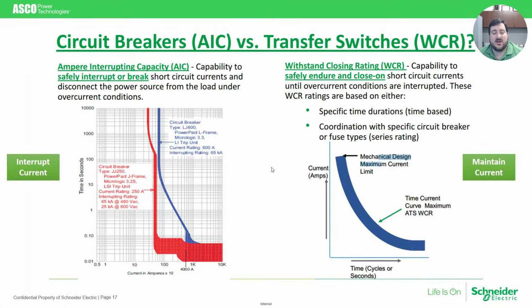I briefly touched on the concept earlier of ratings and what we call WCR ratings. This is more of a UL 1008 terminology, but a very similar concept exists in IEC ratings as well. So I'll just use the UL terminology for the sake of this conversation. Circuit breakers, which many people are familiar with, have a KAIC rating. An ampere interrupting rating is really what that represents. And what that means is, what is the short circuit fault capacity that the breaker is able to safely open under without sustaining extensive damage? So how big is the fault that that breaker is rated to interrupt? And by interrupt, that means opening the breaker to end the fault condition. Its number one job being protection.